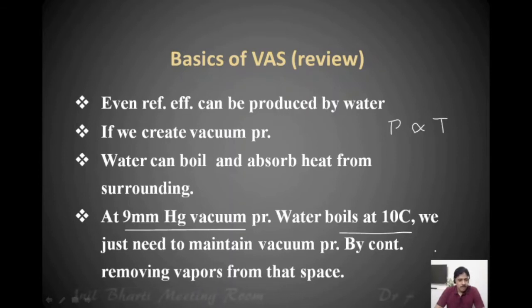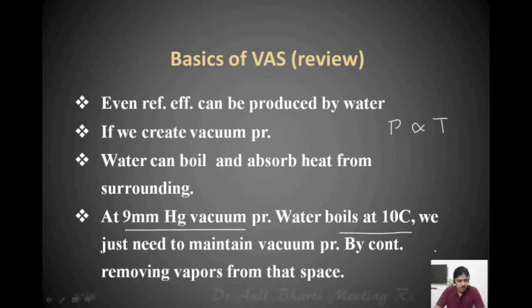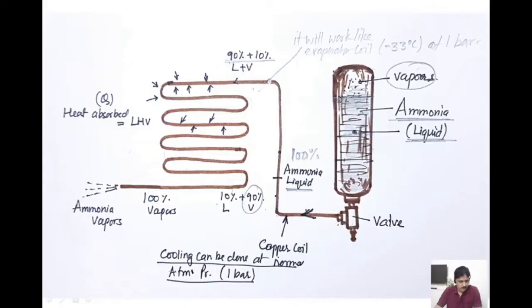So we have designed refrigerants — special liquids that can boil even at atmospheric pressure of 1.01 bar. For example, ammonia can boil at normal atmospheric pressure. If we boil ammonia at normal pressure, it boils at minus 33 degrees Celsius — that is how low a temperature it can maintain. This is a cylinder containing liquid ammonia at around 10 bar pressure with a valve.